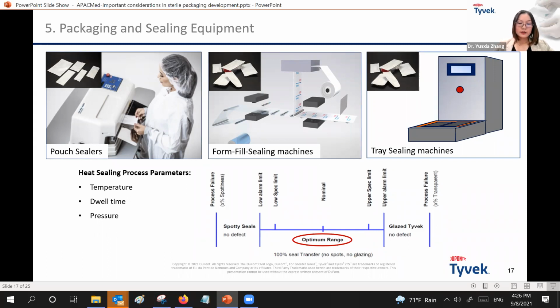So from a visual evaluation perspective, with an optimum range of heat sealing process developed, the sterile packaging manufacturer or medical device manufacturer will be able to get a good seal transfer with no spots or no glazing. And here you can see we also show some sealing equipment. This is a pouch sealer to seal the other side of the pouch, a form fill seal machine, and an example of a tray sealing machine.